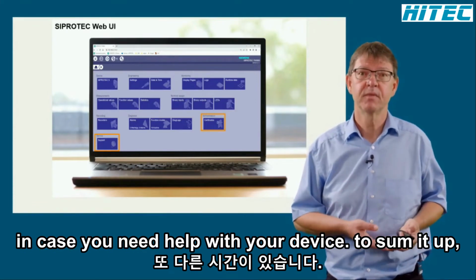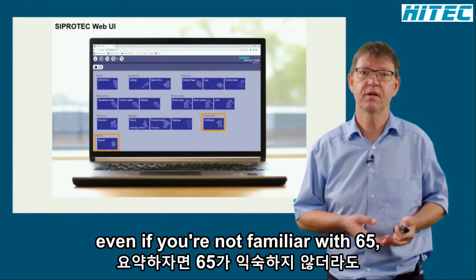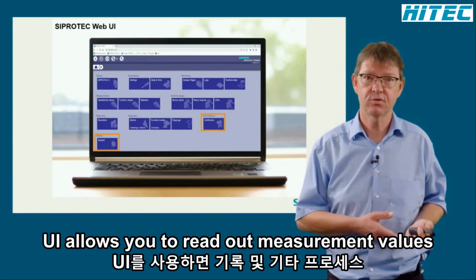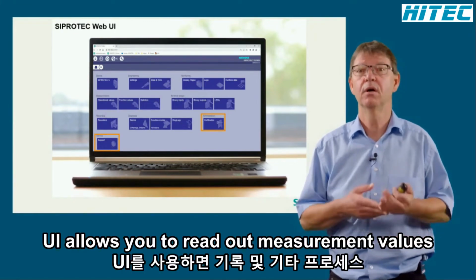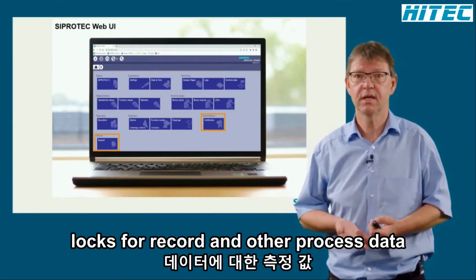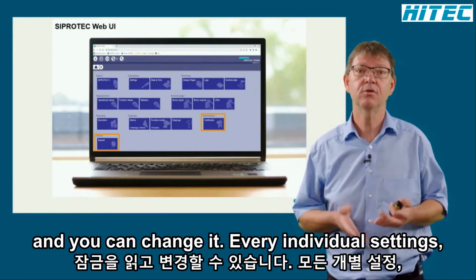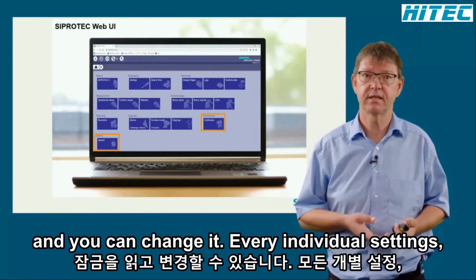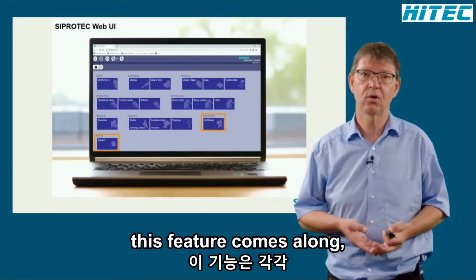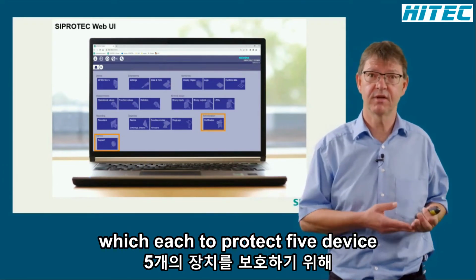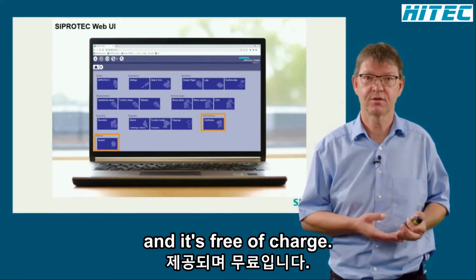To sum it up, even if you're not familiar with DIGSI 5, the Web UI allows you to read out measurement values, logs, fault records, and other process data, and you can change individual settings. This feature comes along with each SIPROTEC 5 device, and it's free of charge.